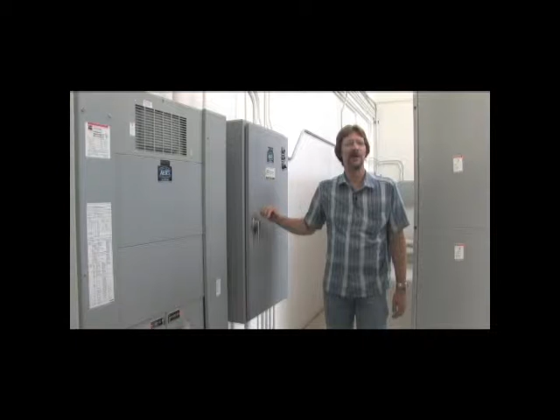So what happens is the power goes out, the UPS switch kicks in, continues to feed power to the emergency lighting and the servers in the data center, and the generator starts up. After 60 seconds of the generator running, this switch activates and feeds power back up to the UPS and all those other systems, including the cooling in the data center. Once the power is restored, this will continue to run for about 60 seconds and then switch off just to make sure everything is stable before it switches.